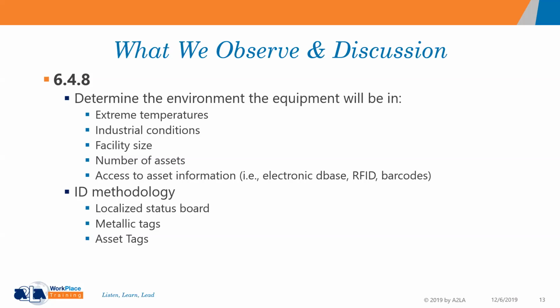So what is it you can do? Well, you have to be creative in this area, and you don't have to necessarily have a tag on everything. You may have something engraved in or etched in glass or something like that that tells you how to trace this back to a database somewhere, or an equipment file in a network or in a paper file. The standard says it has to be readily identifiable, but readily is completely up to you. You can't let the assessors drive you to say, well, readily means from the time I'm sitting here at the audit.